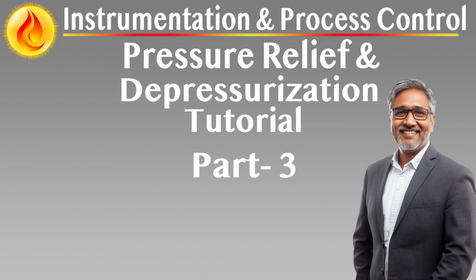Locate valves and piping to allow for routine testing and maintenance with appropriate safe access. Use piping layouts that prevent liquid accumulation, avoid low points, and allow for free draining to reduce risks of hydrate or ice formation. Careful placement of depressurization valves ensures that they function effectively during emergencies while remaining accessible and maintainable throughout the system's life cycle.